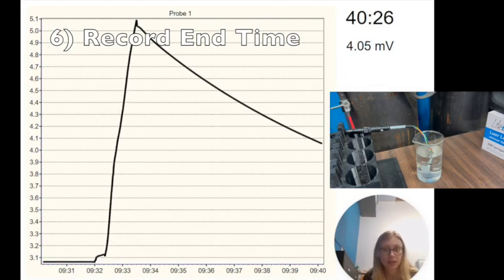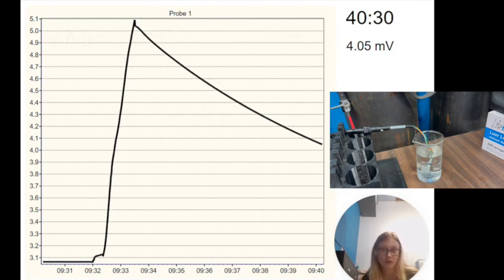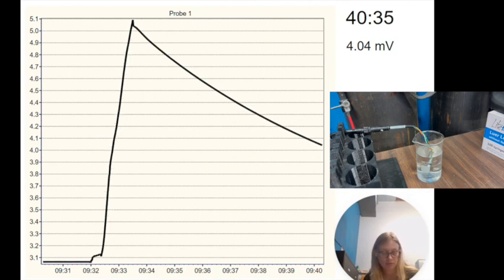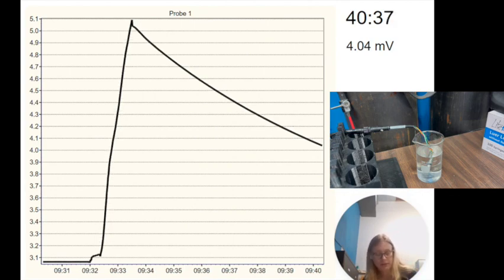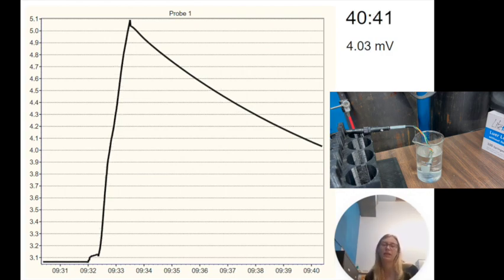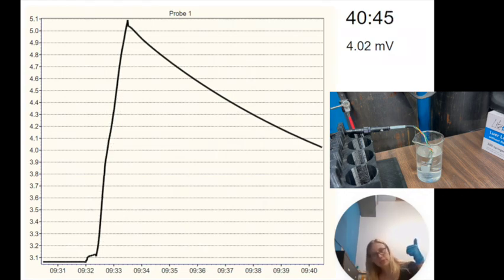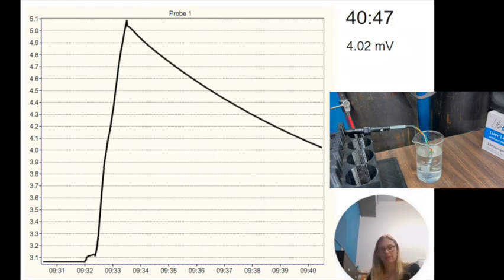Okay, so it took a little under 7 minutes for it to fall back down to 4.06 millivolts. So I'm going to mark it as 40 minutes, 30 seconds. And so this probe would be an example of a pass, because it took less than 3 minutes to climb 2 millivolts and less than 30 minutes to fall 1 millivolt during recovery.